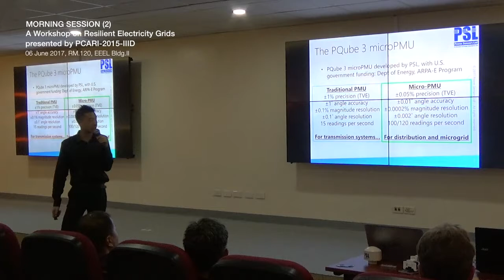So I wanted to talk a little bit about the total vector error. That red circle you see is a 1% boundary. This is one of many tests that we did to validate our design. The red circle is the acceptable limit for a signal that is 120 volts in America, so in the real and imaginary plane, it'll go out to 1.2 volts. We have 4 micro PMUs, with 3 PMUs measuring against one, which we considered the reference. We did 9,000 measurements on all of the PMUs, and they all fell to within 0.05% TVE.